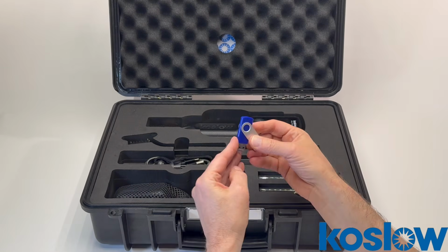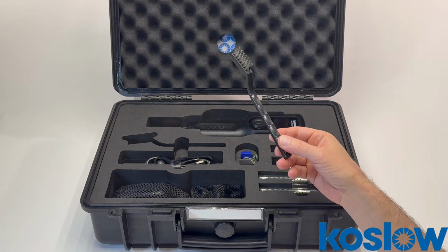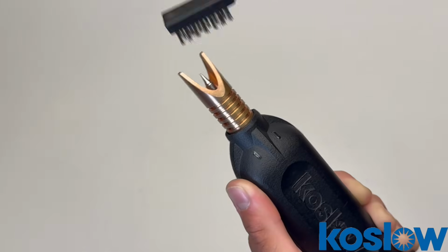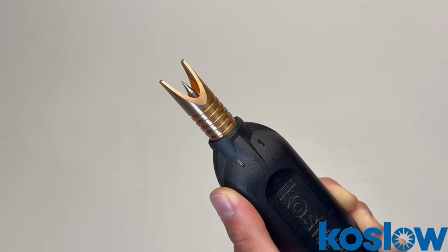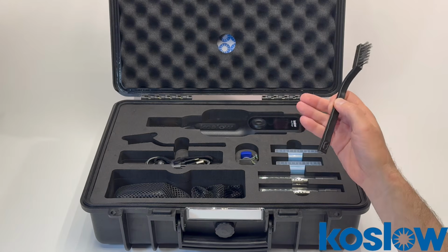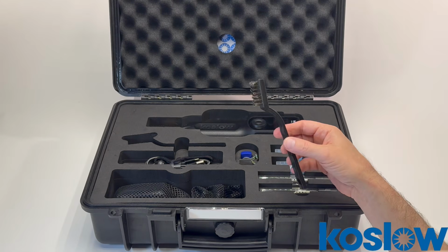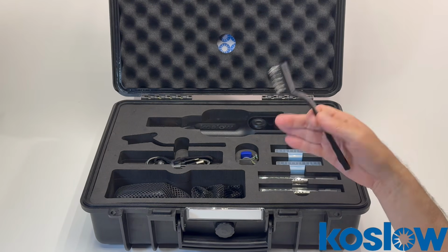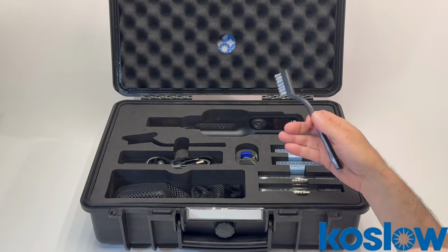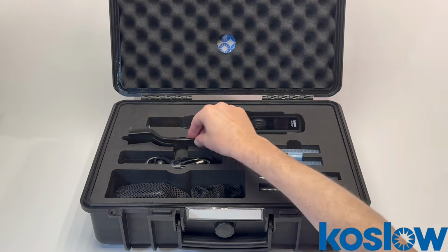Here's a wire brush, used for cleaning the prongs of the machine and the heated tip, as well as the daily qualification standard or any other metal you may want to test. Make sure there's no corrosion, dust, dirt, or paint on the surface of metals.